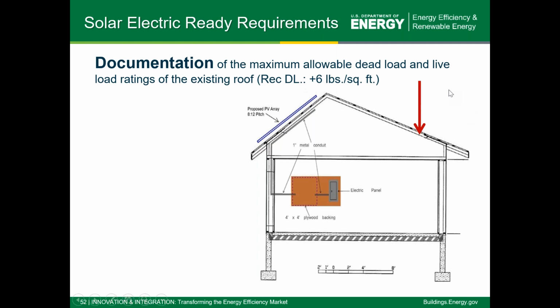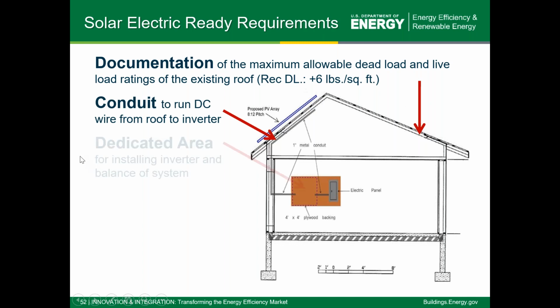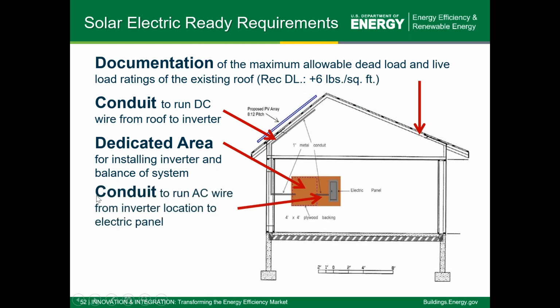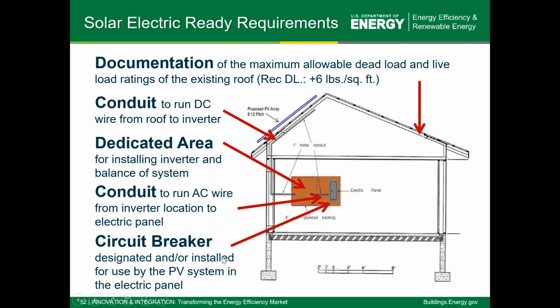For homes that do follow the checklist, here's what they look like: documenting the load ratings on the roof structure so the homeowner has them in hand if needed in the future; running a piece of conduit from the attic area down to the electric service panel so wiring can be fished through at some point; that conduit is capped and labeled; providing a dedicated area for balance of system components like the inverter; running a conduit from that area over to the service panel; and finally, reserving space in the panel itself to add a circuit breaker that ties in a future PV system.